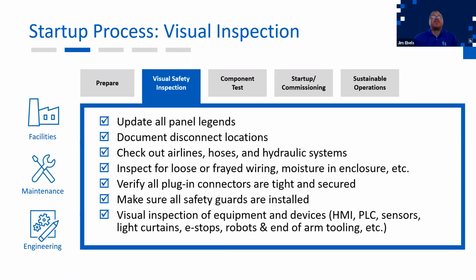And visual inspection of controls equipment and devices. Your HMI and your PLC, checking for visible damage to the screen, any loose or disconnected cables, as Ken mentioned. Sensors and light curtains, same thing, looking for loose connections, any alignment issues, physical damage, and then e-stops. Making sure there aren't any engaged that could have you searching for why your machine won't power up. In terms of robotics and end-of-arm tooling, making sure it's mounted securely, checking for loose bolts, damage to the end-of-arm tooling, and any power and cable connection issues that could be there. Next slide.